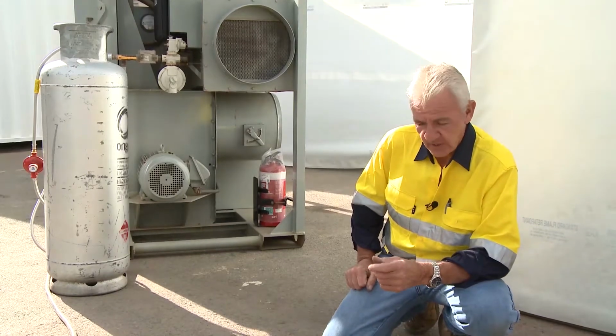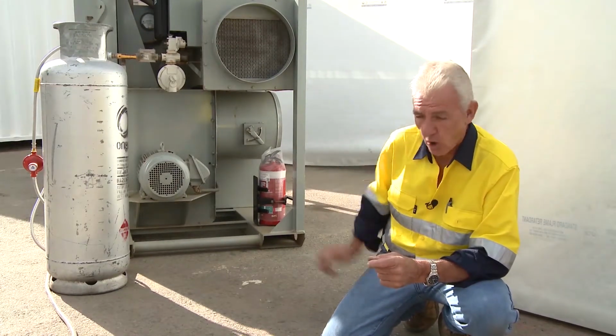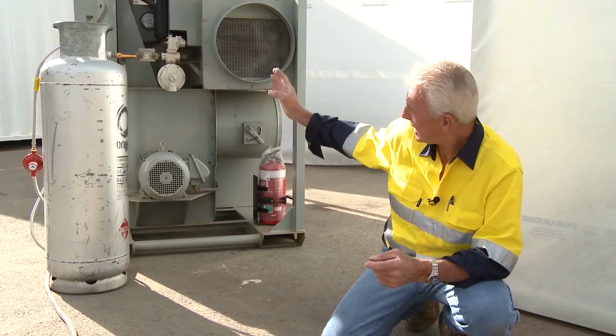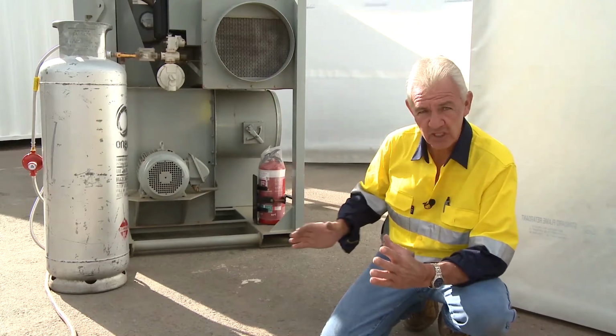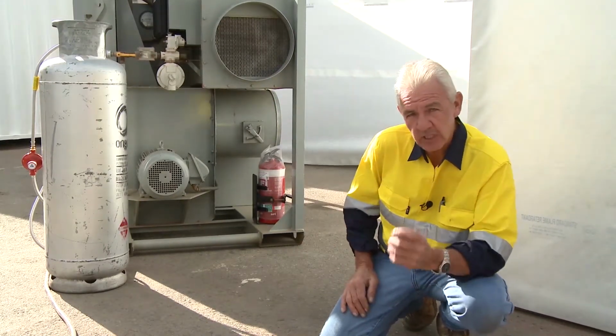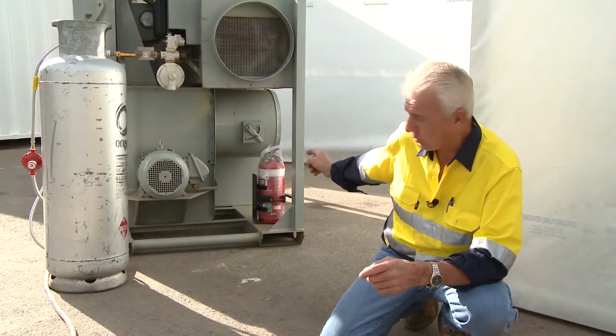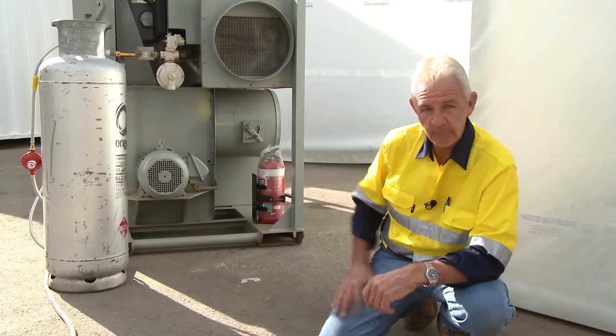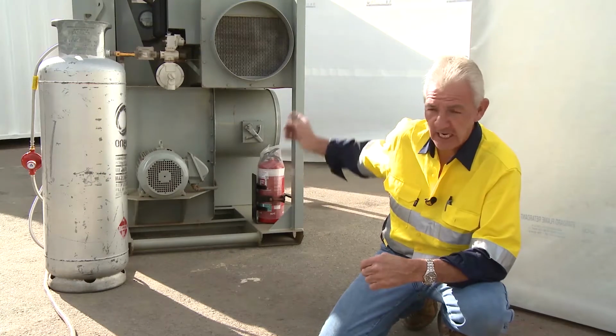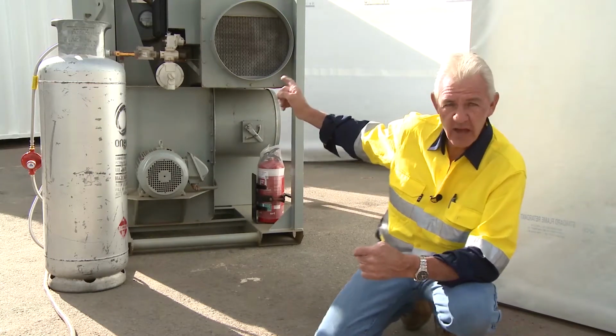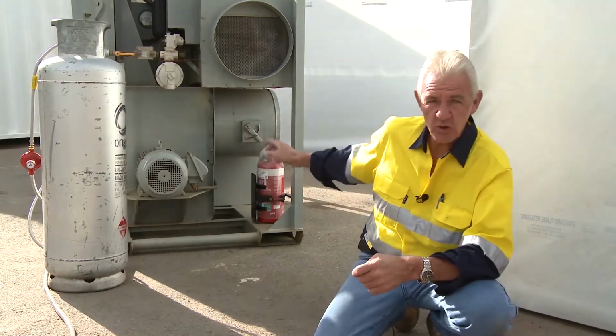Letting that wing nut go and adjusting that butterfly valve alters the pressure within the magnehelic gauge, so it reads it relatively quickly. So what I am saying to you is don't undo the wing nut, just flip the valve open or shut, because it has a detrimental effect on how that free flow of air comes through there.